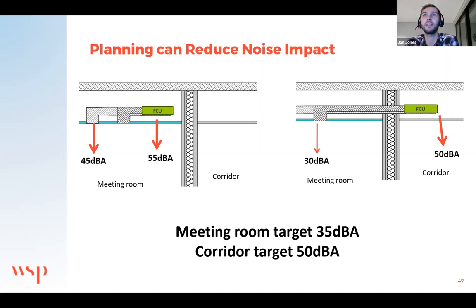So taking this example here, and a comparison of the two, we've got a meeting room on the left with a corridor on the right. If we put the fan coil unit in the meeting room, we've got the two contributions of noise, which we touched on before, which is the sound duct supply noise and also the casing and inlet breakout noise level.